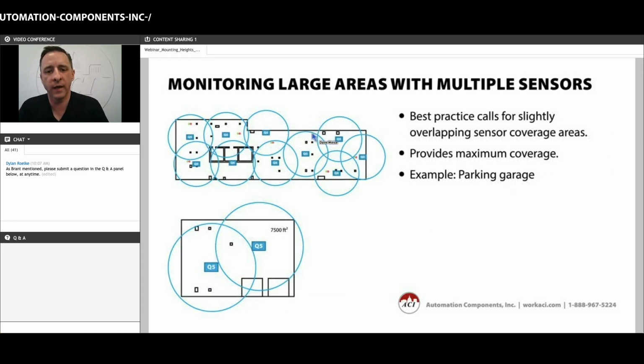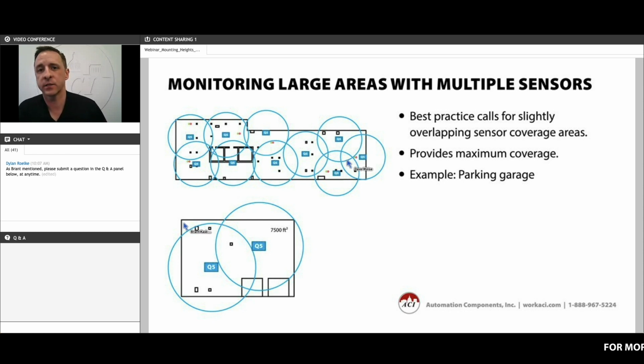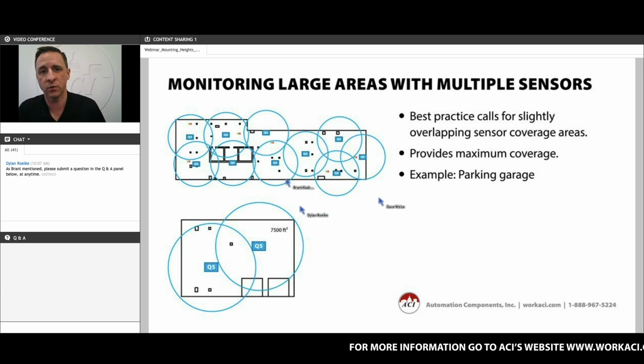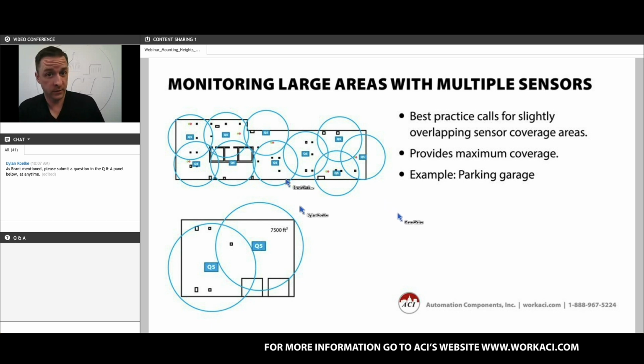We recommend that the sensors be placed so that they slightly overlap to eliminate what we would call dead zones, any areas in a space where gas could accumulate without being sensed. So we want to overlap slightly and also have the sensors placed in as central an area as possible, not only to get the best coverage, but to minimize the number of sensors that you would need and therefore save you money in terms of the total cost of the installation of these gas sensors.